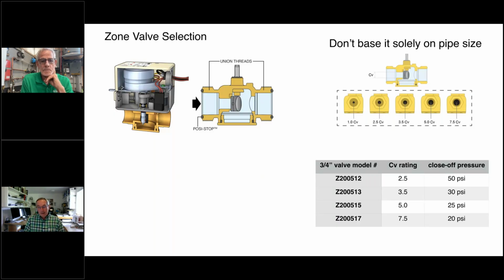Now, again, you can design the system so that a 20 PSI close-off pressure is fine. But you just have to make sure that you're not creating a circuit that has really high differential pressure when it's operating. Upsize the piping, use components that have lower head loss characteristics. But the trade-off is close-off pressure versus CV versus the pressure drop through the valve.